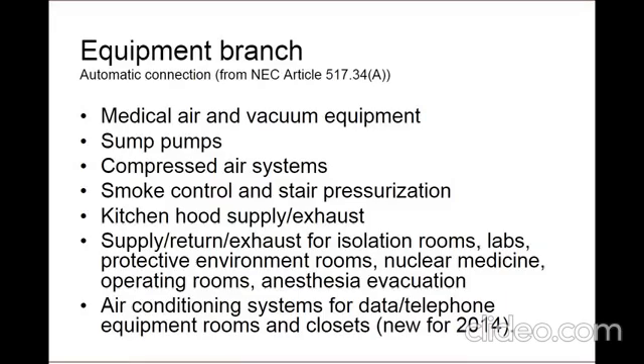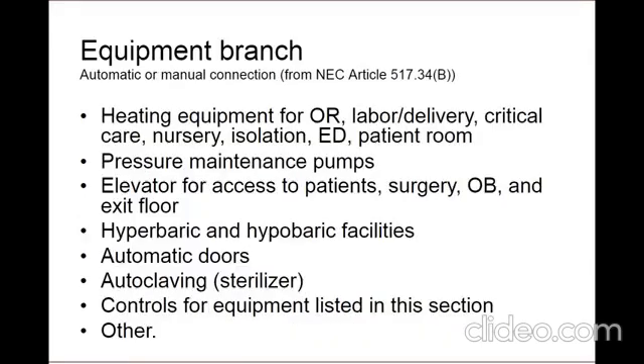Or you can instruct your friendly mechanical engineer to design a dedicated system for these rooms, such as a DX fan coil unit or something that's a little more manageable on the equipment branch system. A couple of exceptions do apply here. The medical air and vacuum systems are allowed to be on the critical branch, and a handful of other things. Basically any other systems that could potentially be hindered if connected to a delayed connection or on a shuttable branch. So just note there's exceptions there.